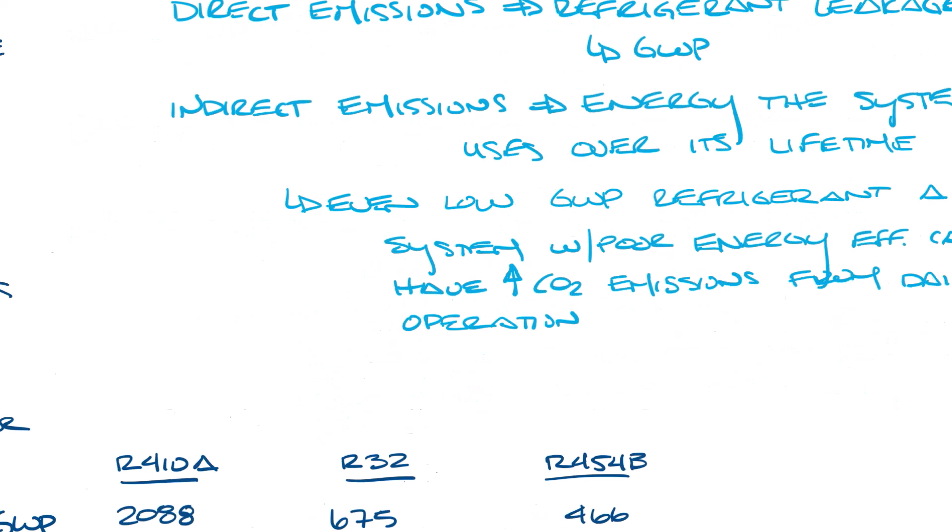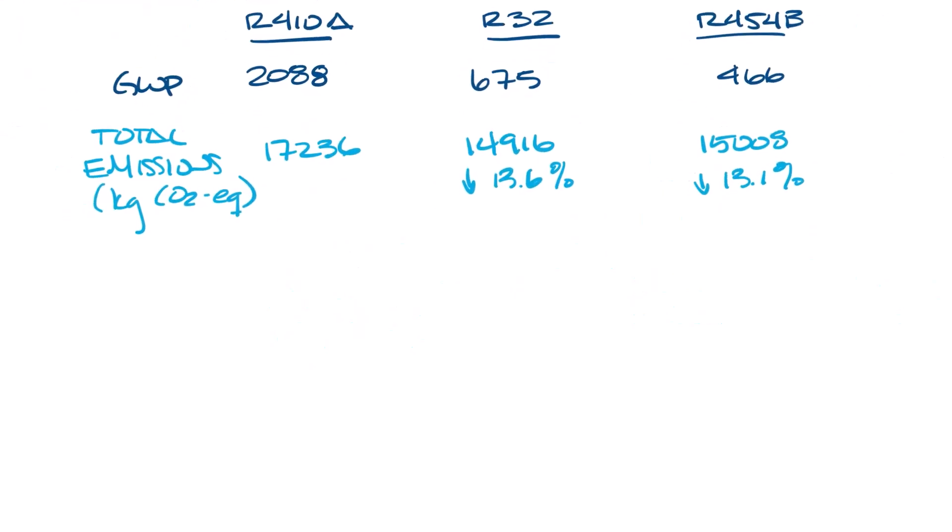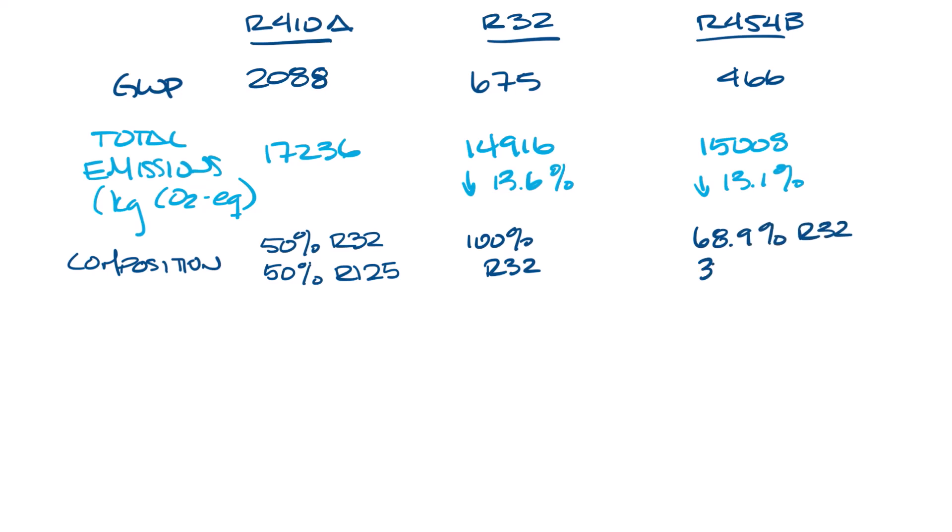Let's move back to our table. So I mentioned in the last video, R410A is a 50-50 mix of R32 and R125. R32 is obviously 100% R32, and R454B is 68.9% R32 and 31.1% R1234YF. This is important because of temperature glide. Because they're blends, R410A and R454B will have temperature glide. R32 is not a blend, so it will not have temperature glide.